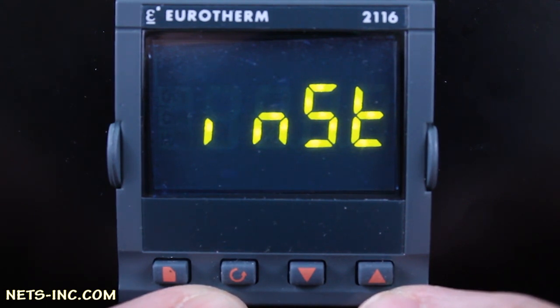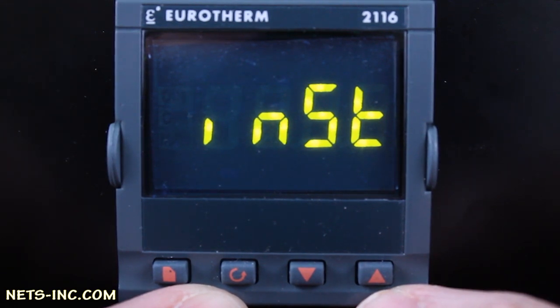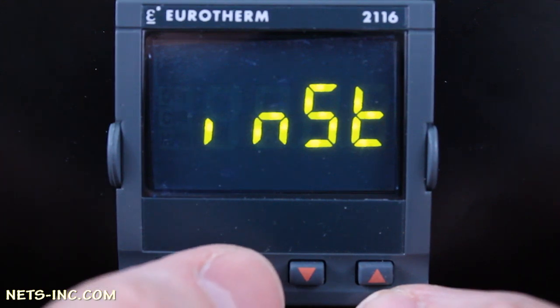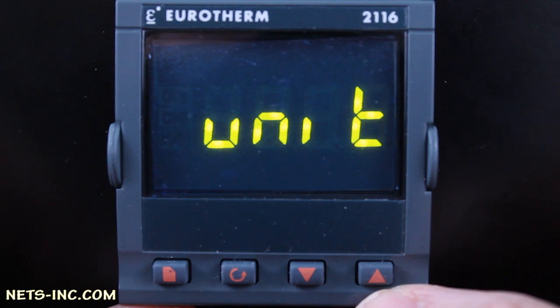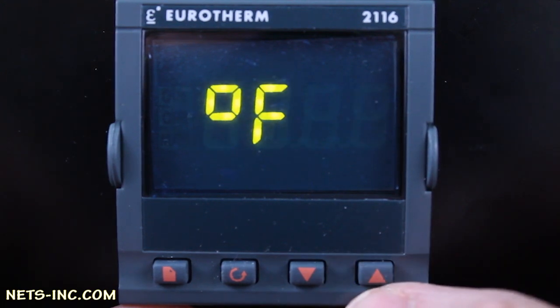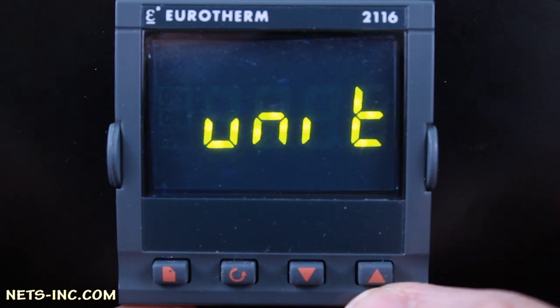Next, we will navigate the INST list of the configuration level and modify the parameters for our application. Note that some parameters are standard and will not be changed — refer to the 2132 or 2116 instruction manual for further detail. With the display reading INST, press the Scroll key once to drill down into the INST list. The display will read 'unit'. Press the Up Arrow and the unit is set to degrees Fahrenheit. Press Scroll again and the display will read 'dec dot p', which is the decimal point setting.